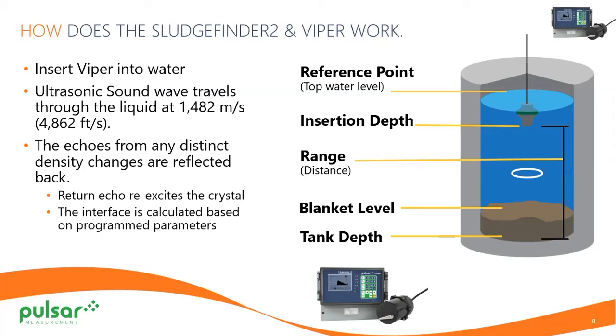It will pick up any distinct density changes in that tank. It also gives you the ability to read flock. So if you wanted to read the sludge level at the bottom and also the flock level, you can program that as well and set up relays to siphon off the sludge off of the bottom.